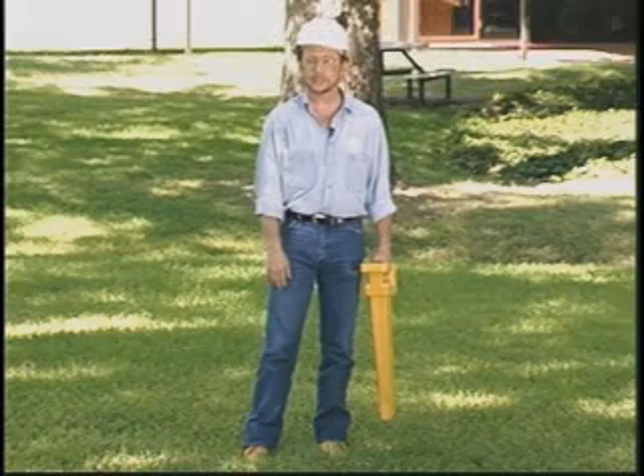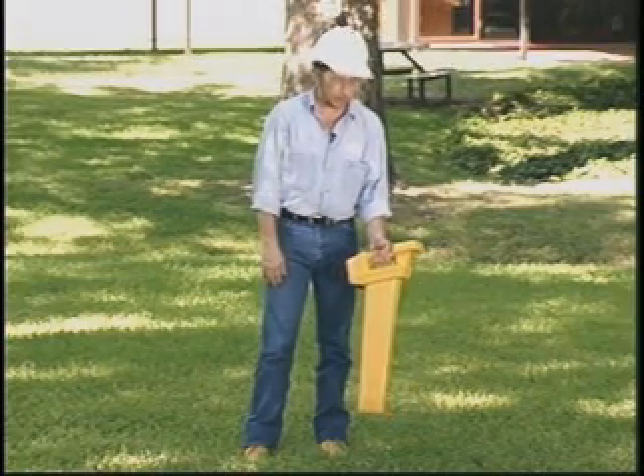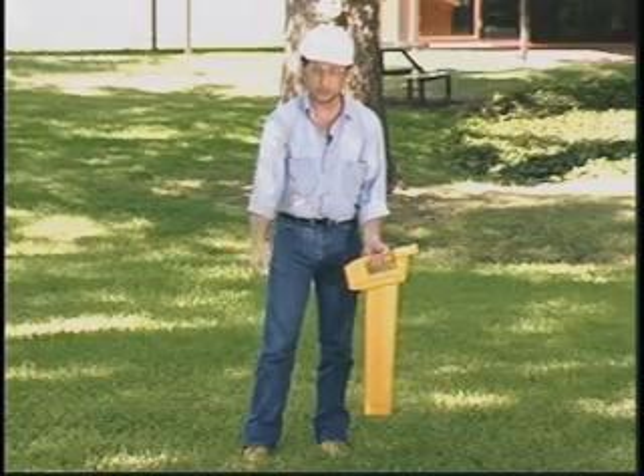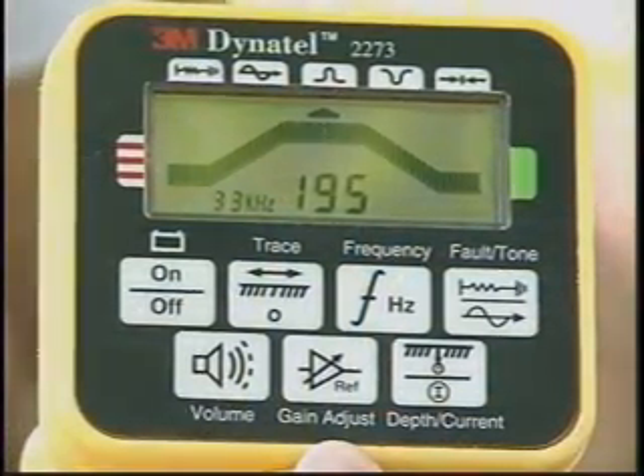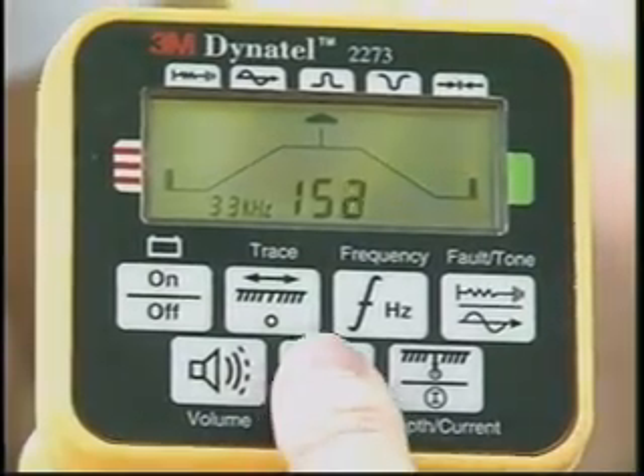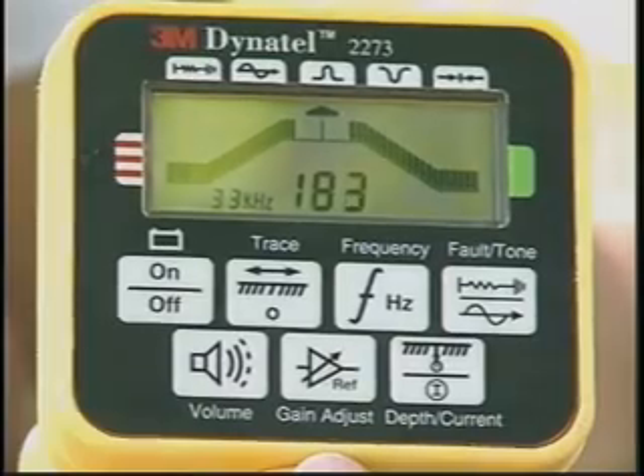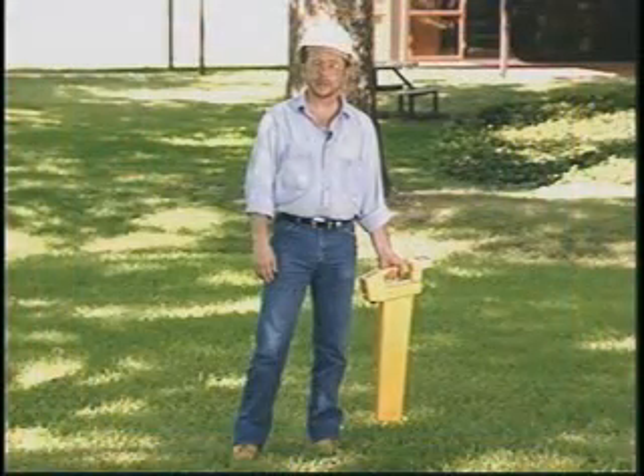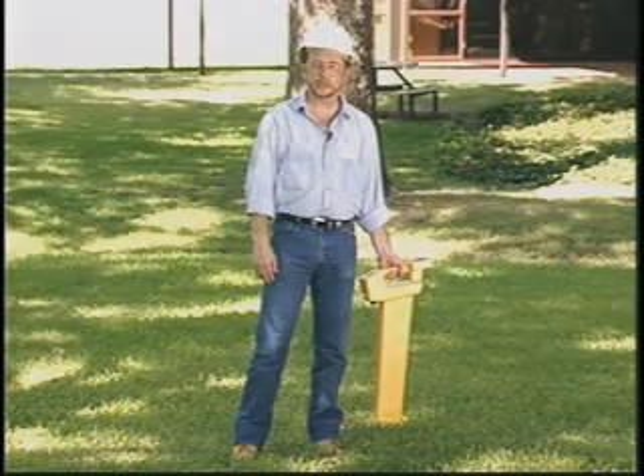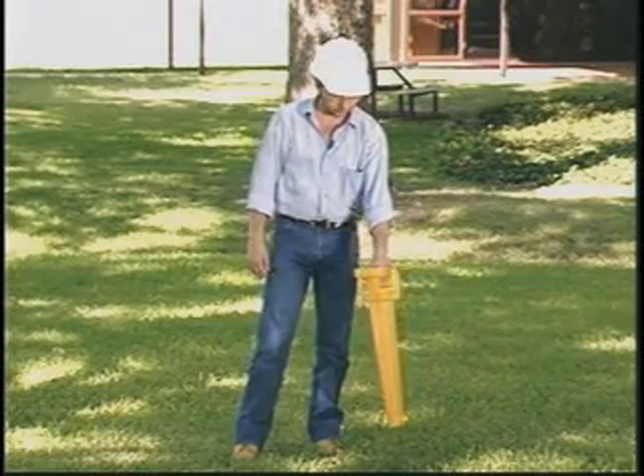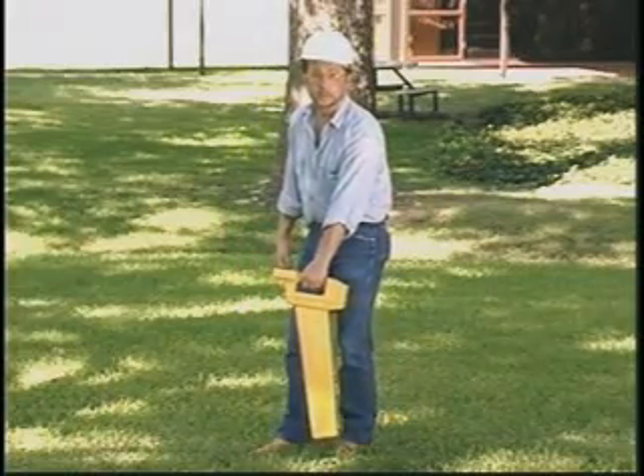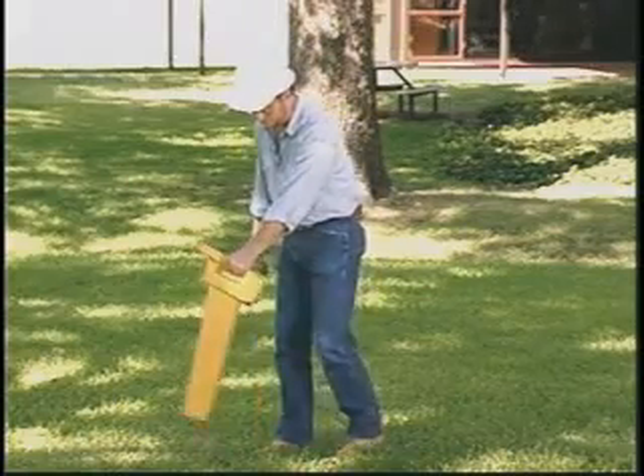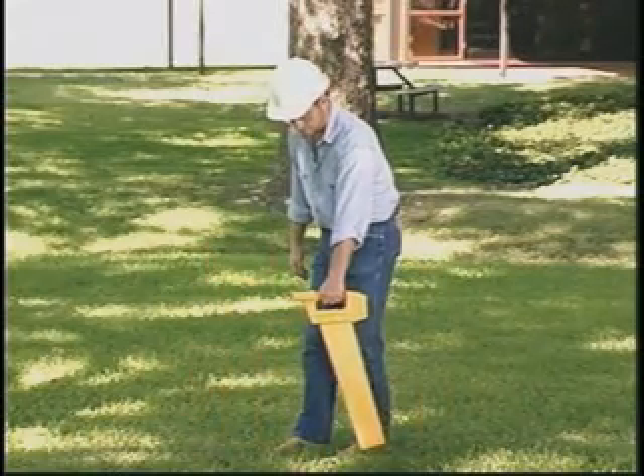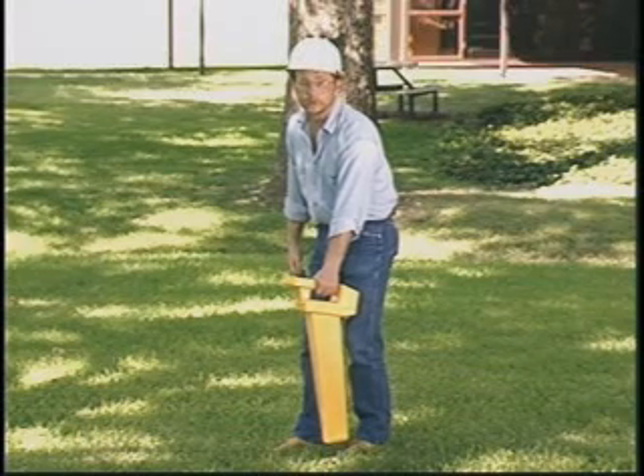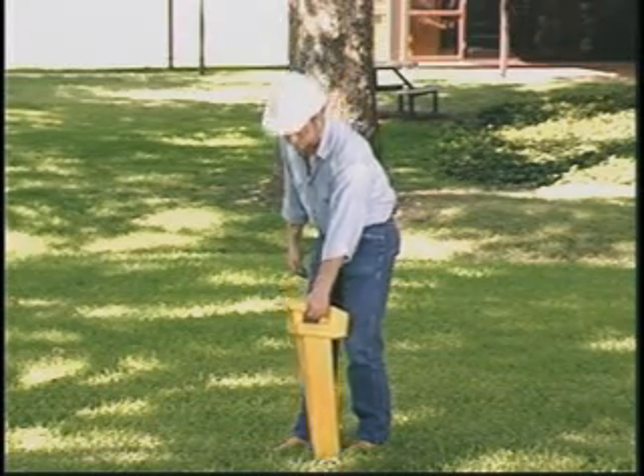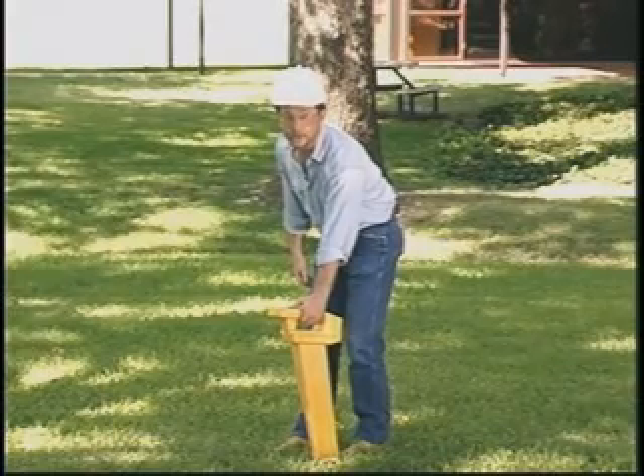You have to hold the receiver so that its handle is perpendicular to the duct path. So I'll hold it like this since the path is in this direction. If the bar graph stays fully closed or fully open as you're tracing the path, press the gain key. To make sure you're directly over the probe, turn the receiver until you get the strongest signal. And then move it across the path until you get the strongest signal again. To measure the probe's depth, set the receiver antenna on the ground directly over the probe and press the depth key twice for ADP depth.